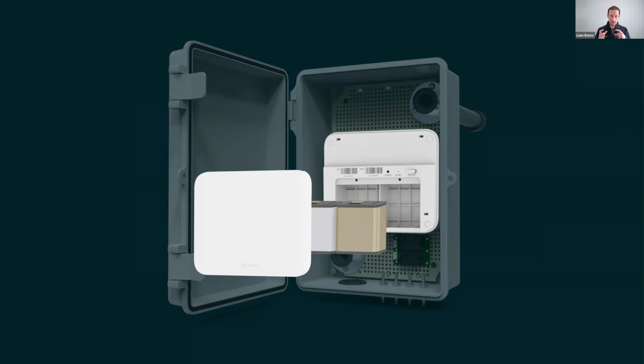So you definitely want the ability to easily recalibrate these sensors. So with this design, you simply pop open the housing, you swap out the module, you put a new one in. The device doesn't even go offline. You don't lose any readings, and you have essentially a brand new sensing element, brand new device here. So this removes one of the biggest complexities around accurately measuring air quality readings within ductwork. You can also upgrade these modules over time as we release new additional parameters, additional modules. So the device itself is designed to last 10 plus years, and you can always make sure that you have the latest technology and the latest sensing elements simply by swapping out these modules.